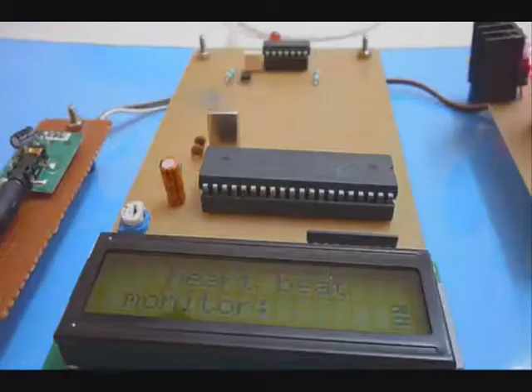Now let us see the operation of our module. First, the finger of the patient is placed between these two plates of the heartbeat sensor clip. Now the light passes from the LED through the finger and gets reflected from this reflector plate, and it is again received by the photodetector, which is placed near this LED. This photodetector receives a signal and passes it as output to the Schmitt trigger. In this Schmitt trigger, there is a threshold value. The Schmitt trigger compares the obtained input with the threshold value for 20 milliseconds and provides the output. This output then triggers our microcontroller.